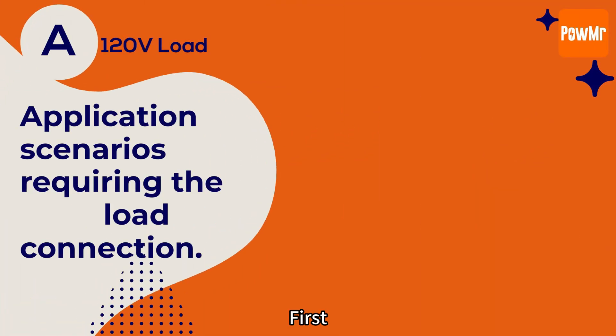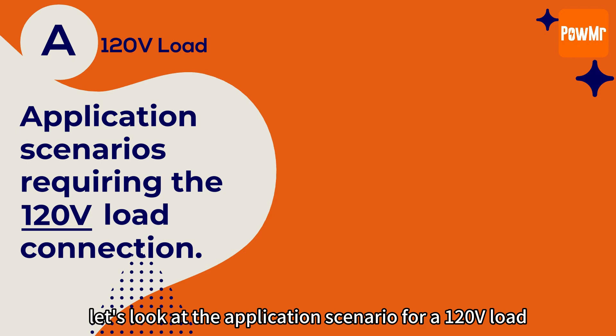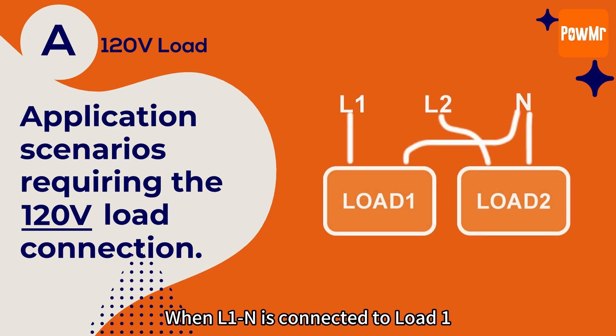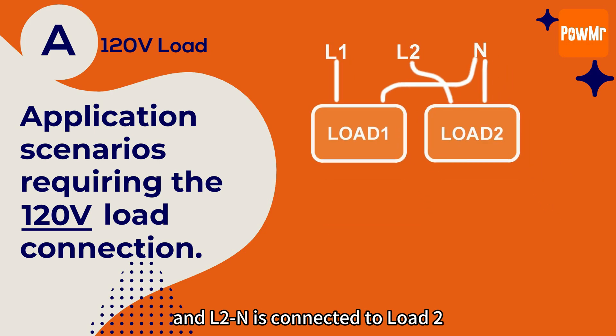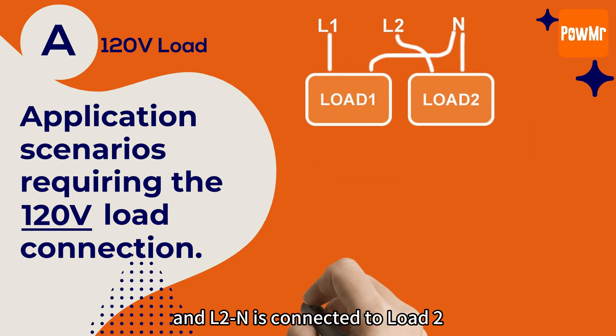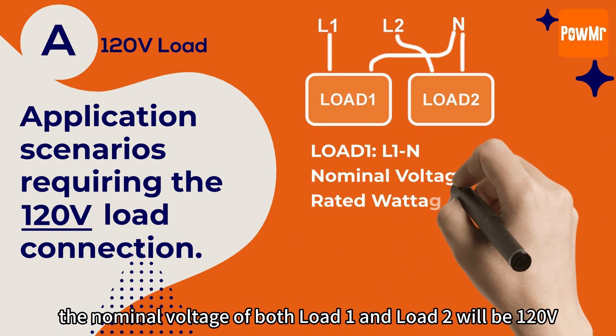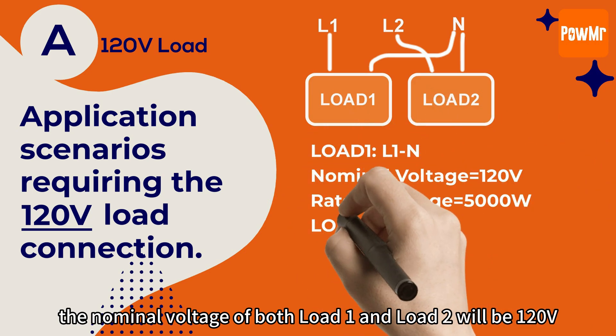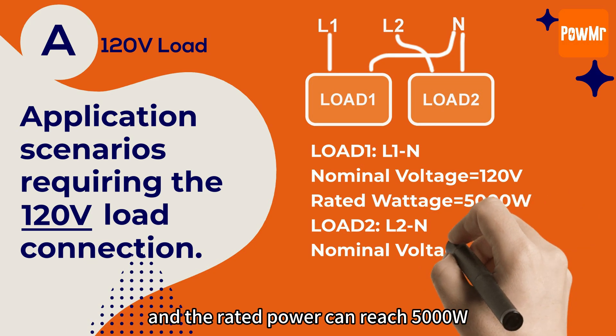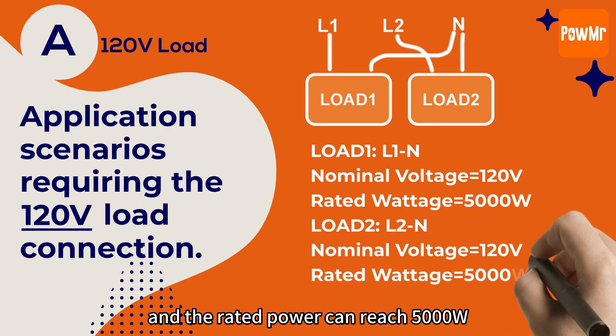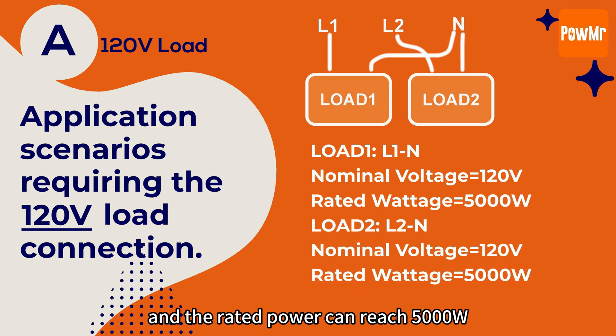First, let's look at the application scenario for a 120V load. When L1N is connected to load 1 and L2N is connected to load 2, the nominal voltage of both load 1 and load 2 will be 120V, and the rated power can reach 5,000W.